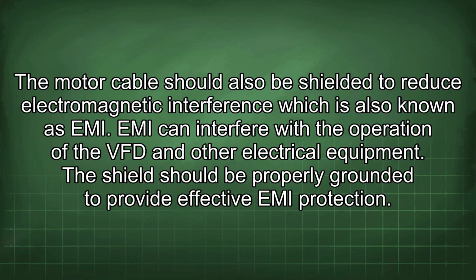The motor cable should also be shielded to reduce electromagnetic interference, which is also known as EMI. EMI can interfere with the operation of the VFD and other electrical equipment. The shield should be properly grounded to provide effective EMI protection.